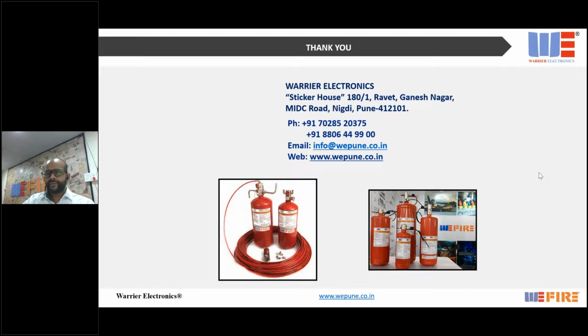I wouldn't say you should replace your regular fire suppression system like the hydrant or sprinkler; this is an addition to those. For a sprinkler to activate, the whole room has to be under fire. If we identify which equipment in that room can start a fire, and protect those, there may not be a need for sprinklers to activate, because we are attacking the source of the fire. So if we identify the machines that can start fire and protect them, we can knock down the fire at a very early stage, and there would not be a need to use a fire hydrant or sprinkler.